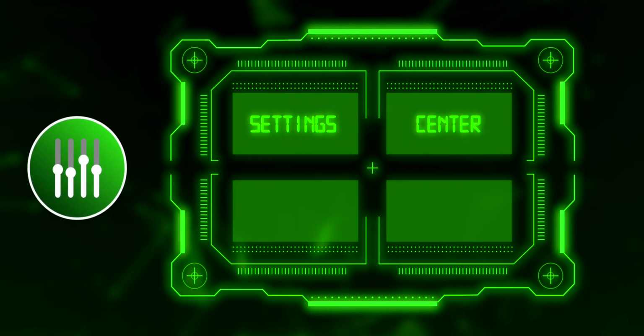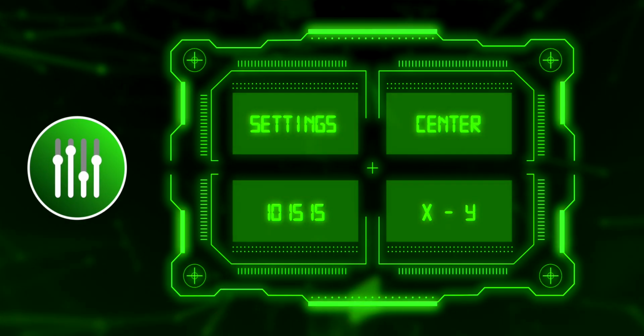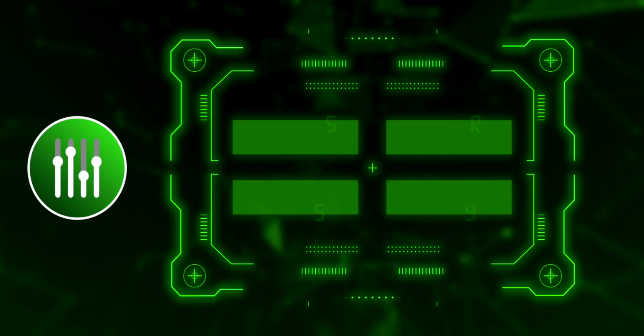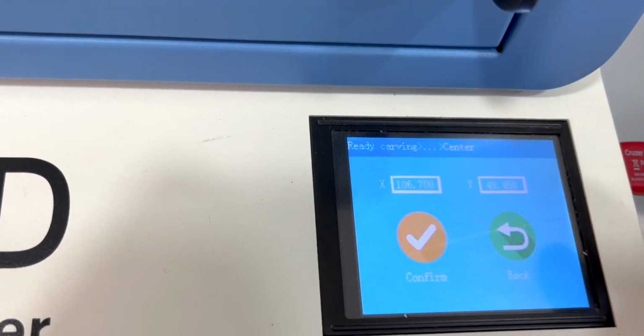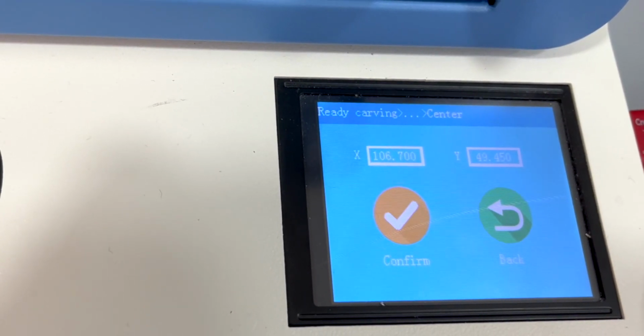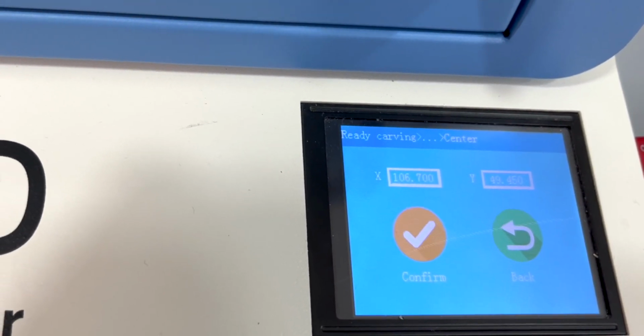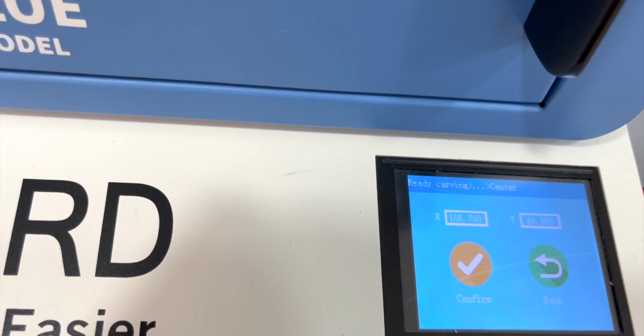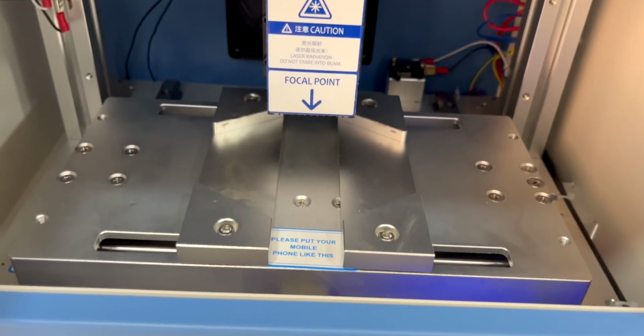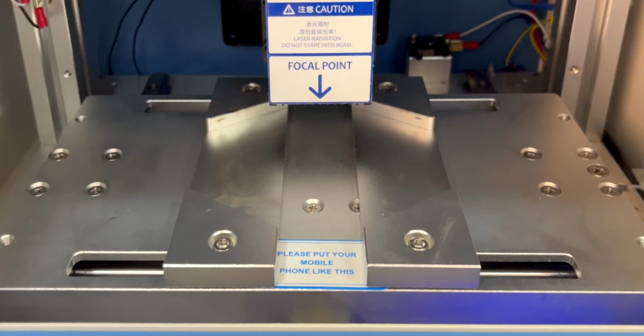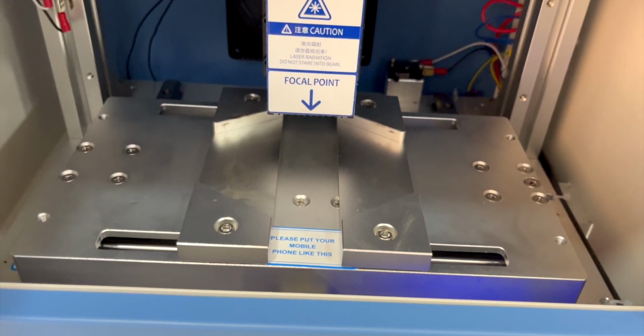We look for them as follows: settings, center, type in code 101515, and we see that it corresponds to Y 49.450 millimeters and X 106.700 millimeters. The next thing we'll do is to interpret what adjustment each axis, X and Y, needs on my own machine. If it needs more or less numbers to be calibrated, that is, should I add or subtract millimeters?